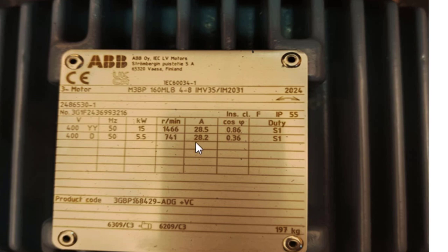So this means that you will get a high input power, the same current of star-star, but you will never get the output mechanical power as the star-star because it has a lower efficiency. So the delta connection is not very good. Nowadays we are using an ordinary induction motor and we will connect a variable speed drive for it to control the speed, and at the same time we will get very good efficiency.